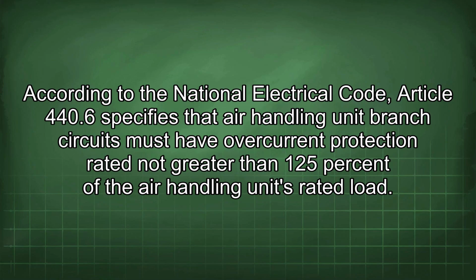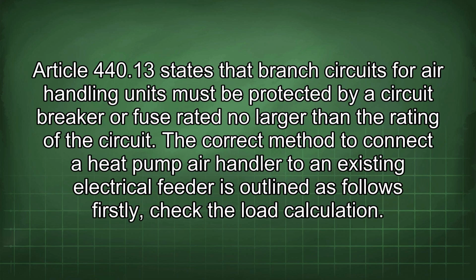According to the National Electrical Code, Article 440.6 specifies that air handling unit branch circuits must have overcurrent protection rated not greater than 125% of the air handling unit's rated load. Article 440.13 states that branch circuits for air handling units must be protected by a circuit breaker or fuse rated no larger than the rating of the circuit.